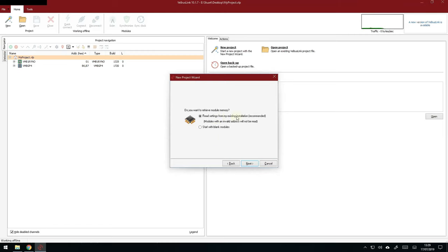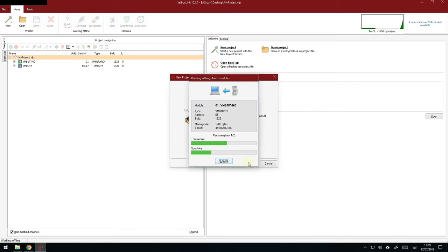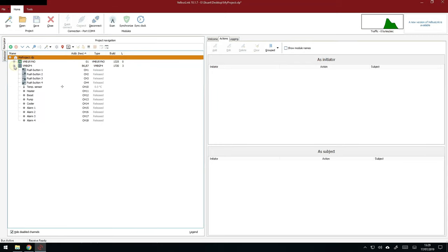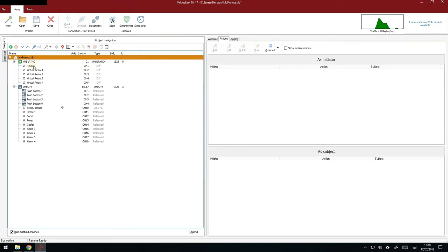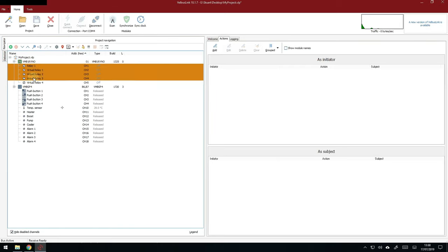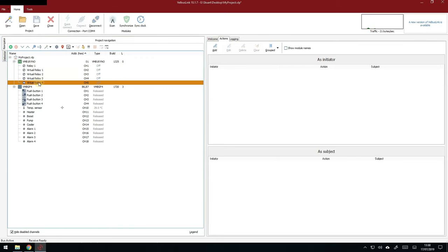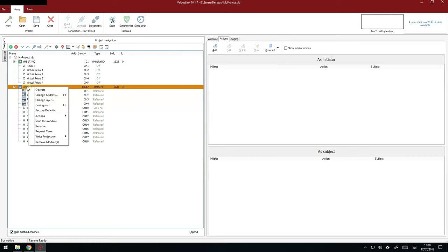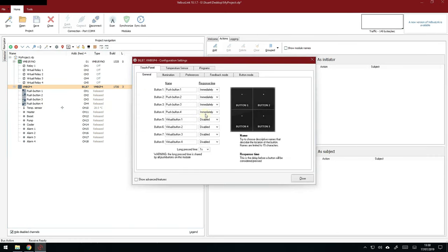We just need to tell it what to do. So, before we go any further, we're going to read the settings from the modules. Because you might be going to an existing installation. So, always read the settings. It's good practice. Someone might have changed something. An alarm time might have changed. Some states might have changed. And it's always nice to capture those before you start doing anything with them. So, let's open up the glass panel, the GP4. And we can see we've got the four real world buttons indicated there. And if we open up the relay, we've got the single channel relay and four virtual relays. If this was a four channel relay, you'd have four real world and one virtual. You can use the virtuals for interlocks and security things and advanced logic, OR gates and AND gates, that sort of thing. Now the glass panel, although it shows four physical buttons, if we look at the configure option, you'll see it's actually configurable for eight buttons.